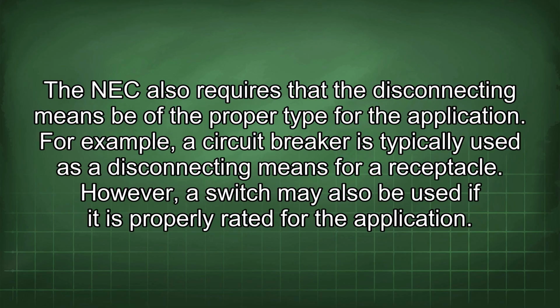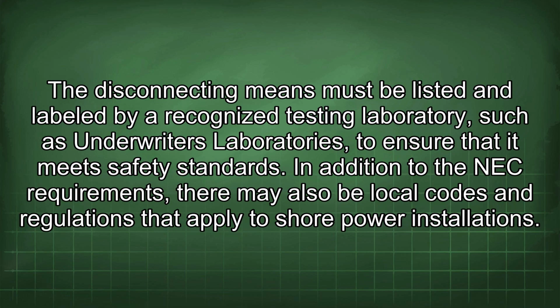The NEC also requires that the disconnecting means be of the proper type for the application. For example, a circuit breaker is typically used as a disconnecting means for a receptacle. However, a switch may also be used if it is properly rated for the application. The disconnecting means must be listed and labeled by a recognized testing laboratory, such as Underwriters Laboratories, to ensure that it meets safety standards.